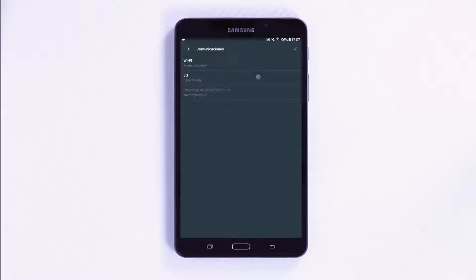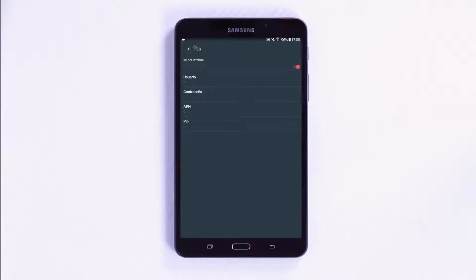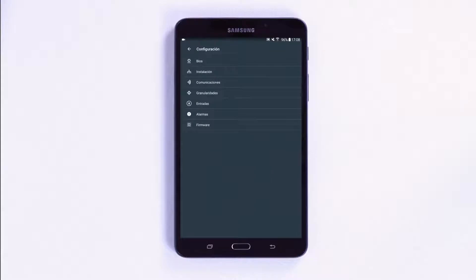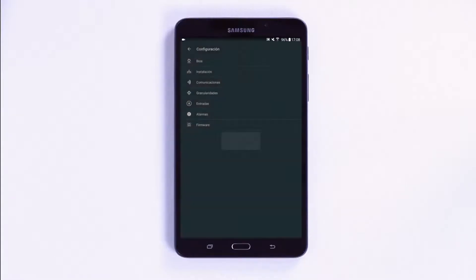On this menu, you can also configure the 3G connection. If you insert a SIM card with a public IP address into the unit and configure the user, password, APN and PIN number parameters, the unit will connect to the Internet via 3G. Remember to save the changes by pressing the Confirm button located in the top right corner.